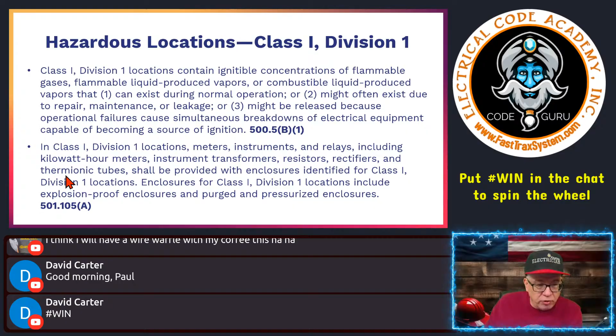These shall be provided with enclosures identified for Class 1 Division 1 locations. So as an electrician, all I know is if it says that, then it has to be in a Class 1 Division 1 location - it has to be an enclosure identified for that, that part I know. Enclosures for Class 1 Division 1 locations include explosion-proof enclosures and purged and pressurized enclosures. This is all out of 501, which is very specific to Class 1 applications. Remember, 500 is very broad, giving you the overview of how to determine the class and division, then 501 gets very specific to flammable gases, vapors, and things like that.